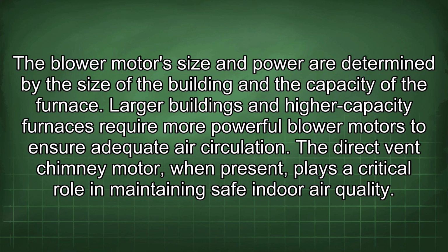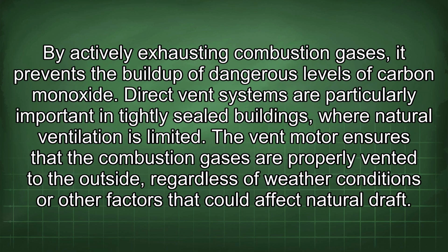The direct vent chimney motor, when present, plays a critical role in maintaining safe indoor air quality. By actively exhausting combustion gases, it prevents the buildup of dangerous levels of carbon monoxide. Direct vent systems are particularly important in tightly sealed buildings where natural ventilation is limited. The vent motor ensures that the combustion gases are properly vented to the outside, regardless of weather conditions or other factors that could affect natural draft.